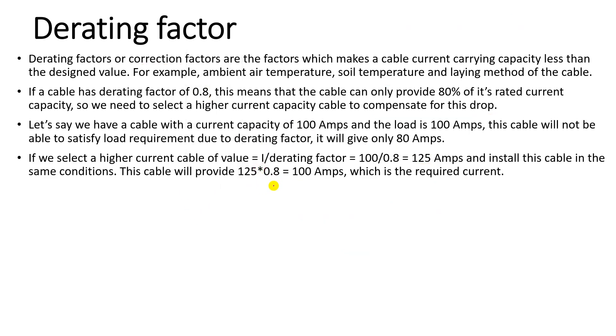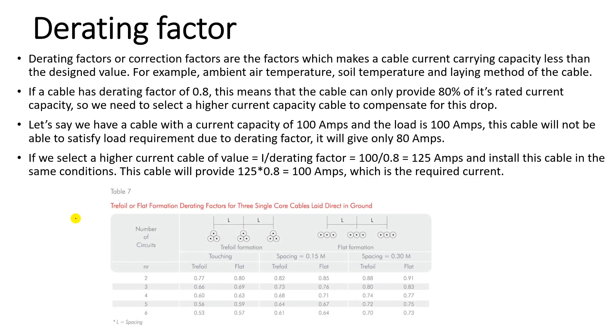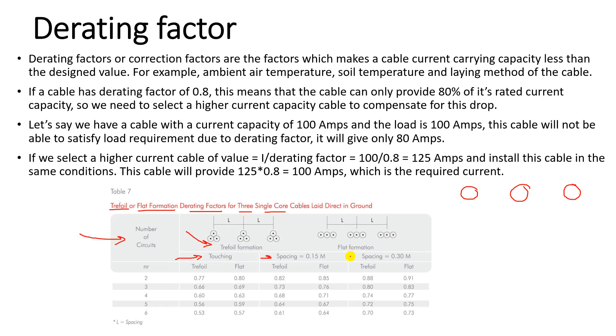This lesson focuses on the derating factor due to cable formation. In the catalog you will find tables for the trefoil and flat formations for single-core cables. The tables also include the number of circuits, the formation type, and whether the cables are touching or have spacing between them.